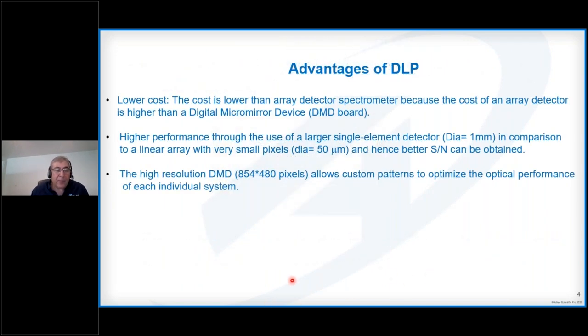This brings about certain advantages and disadvantages for DLP. Let's talk about the advantages first. Because the cost of the micromirror array is less than the detector array, it will reduce the cost of the spectrometer. DLP spectrophotometers are significantly less expensive because the parts are less expensive. Secondly, because a single point detector is used instead of an array detector, you can increase the size, and this increases the signal-to-noise ratio.